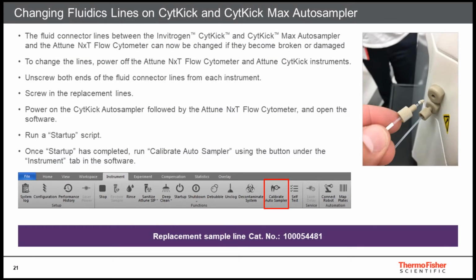Next, ensure there are no cracks or issues found with the fluidic lines connecting the Attune NxT Cytometer to CytKick or CytKick Max. Please change out the lines if needed. And after startup, please run Calibrate Autosampler. CytKick calibration also calibrates the volume in the lines in addition to the location of the probe. The calibration of volume ensures there are no leading data gaps during sample acquisitions from wells.